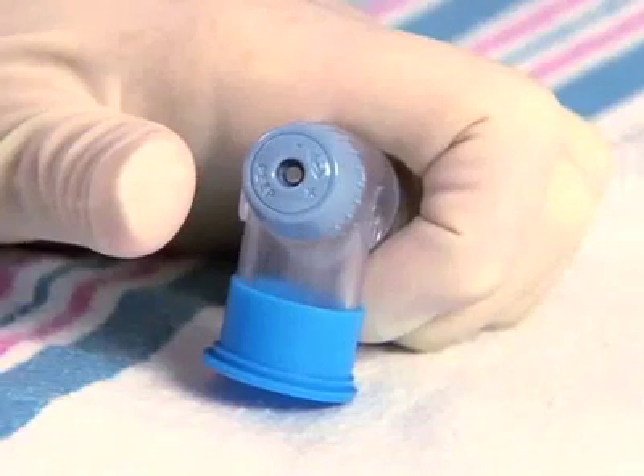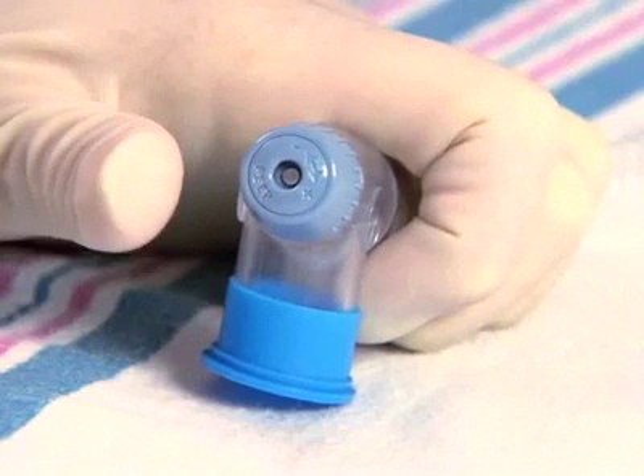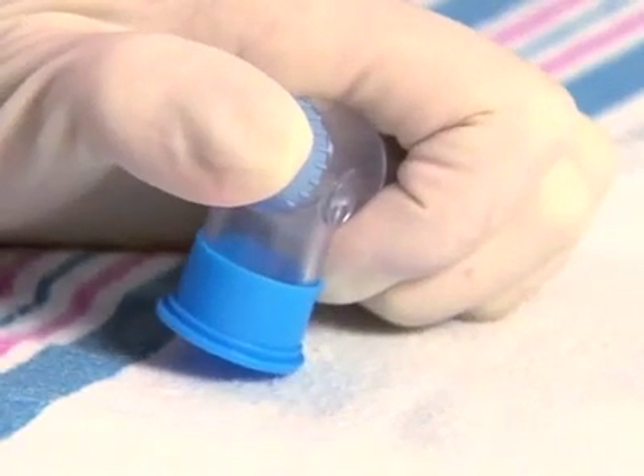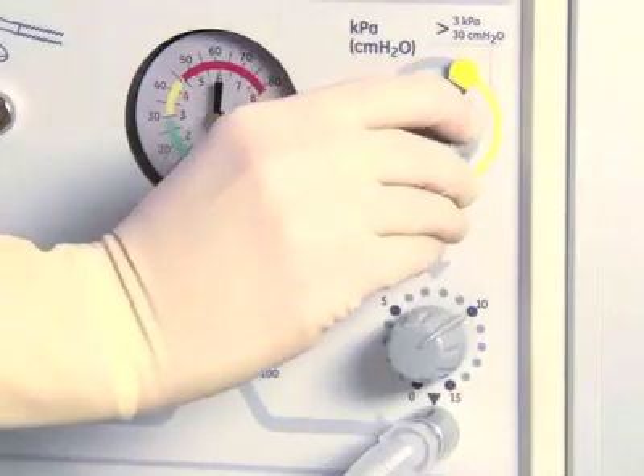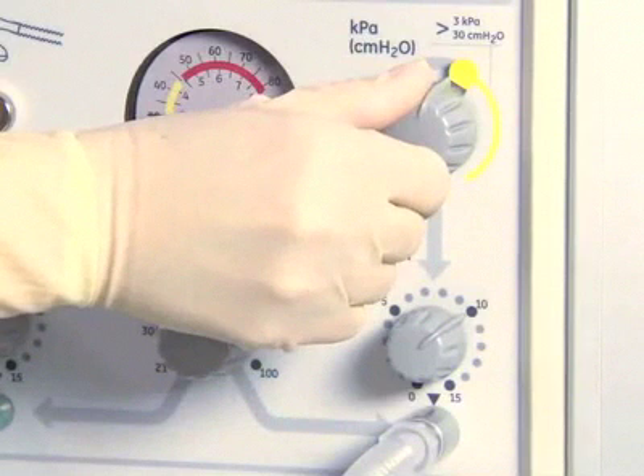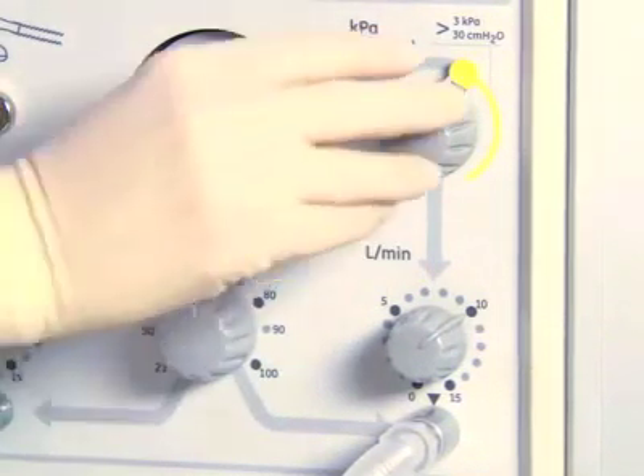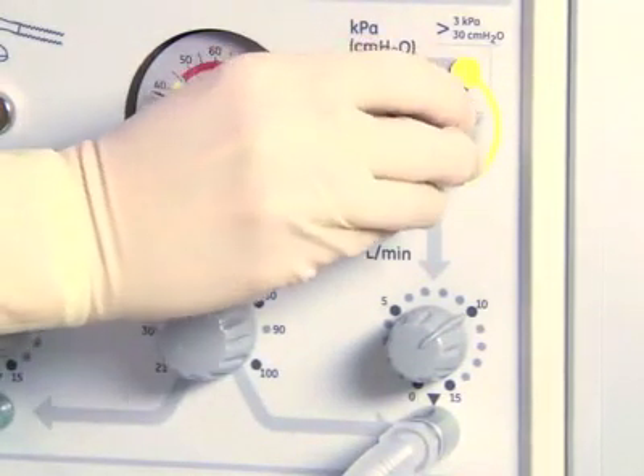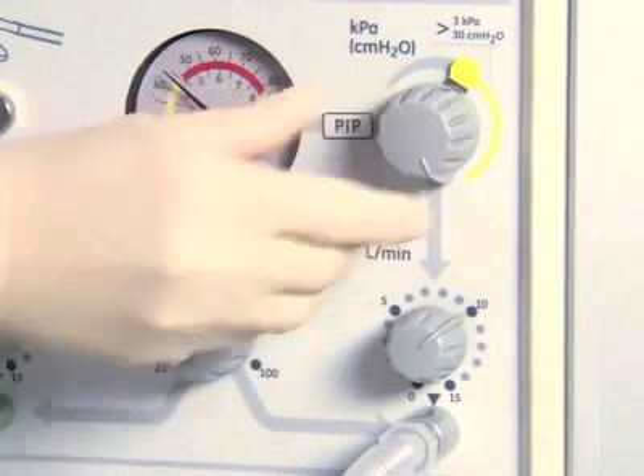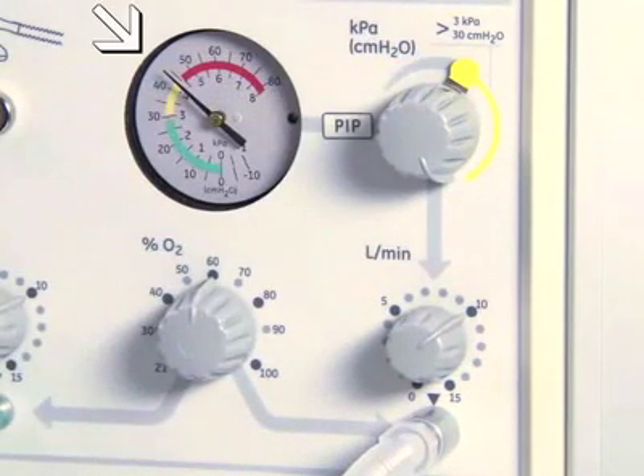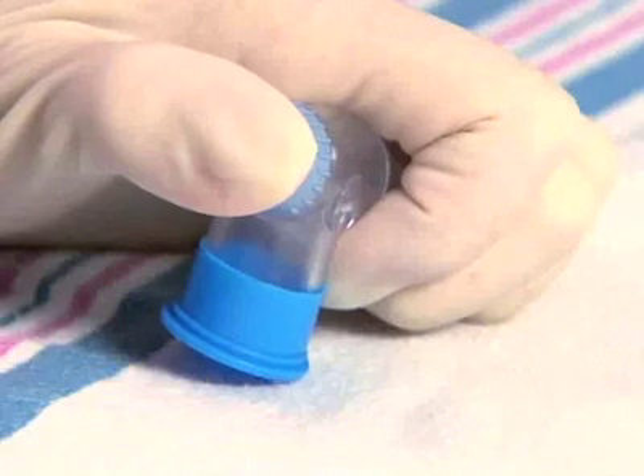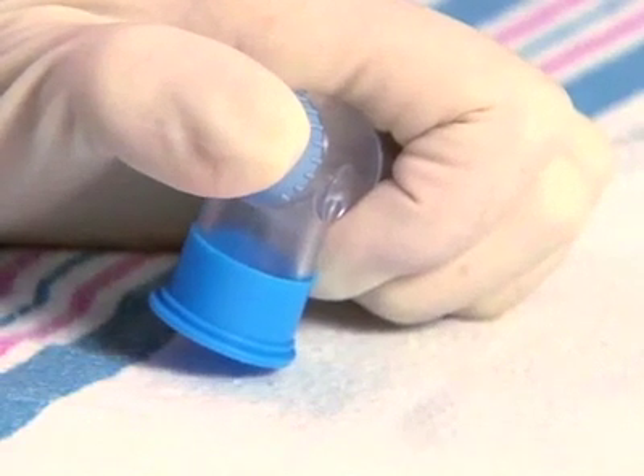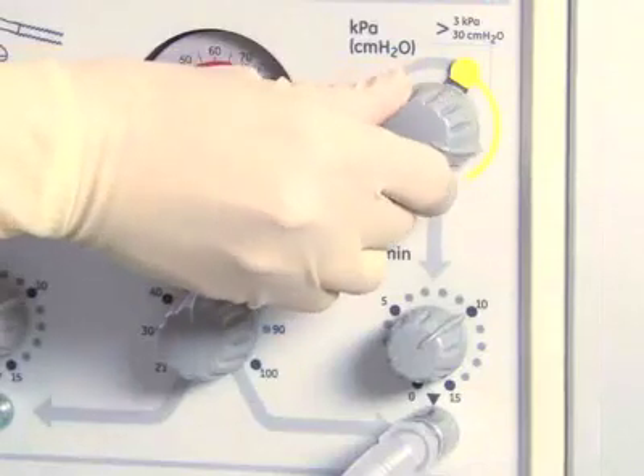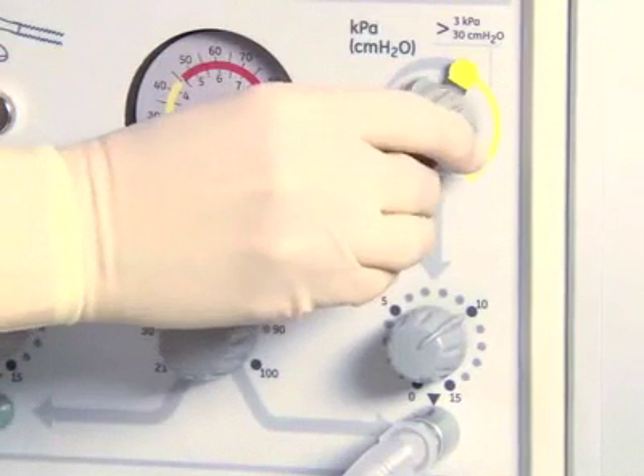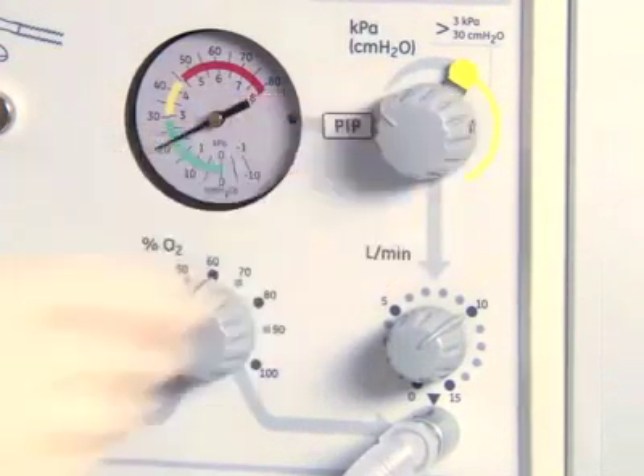To check maximum inspiratory pressure, occlude the PEEP control knob on the T-piece circuit and turn the PIP control knob on the front panel fully clockwise beyond the yellow override release. Verify that 45 centimeters of water pressure can be obtained plus or minus 10% on the airway pressure manometer. While keeping the PEEP control knob on the circuit occluded, turn the PIP control knob on the front panel counterclockwise to set the desired PIP level.